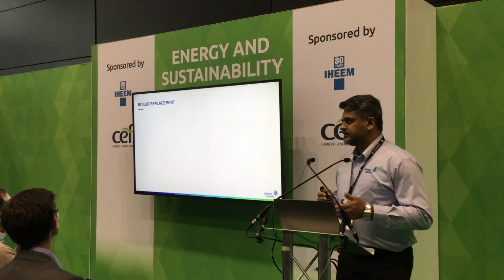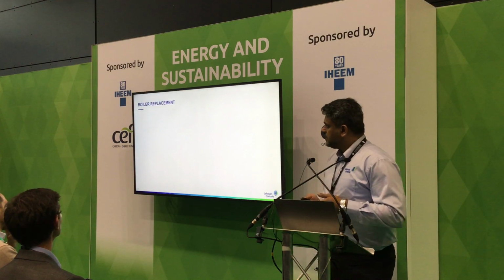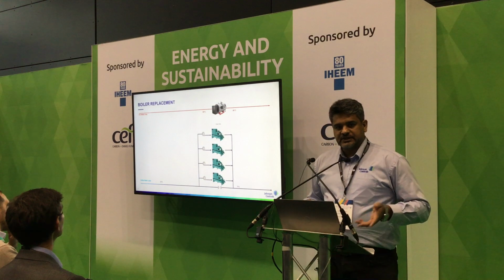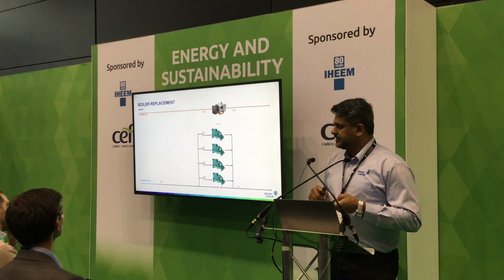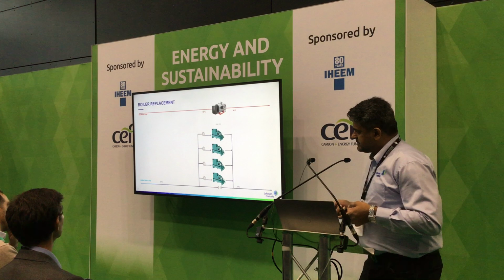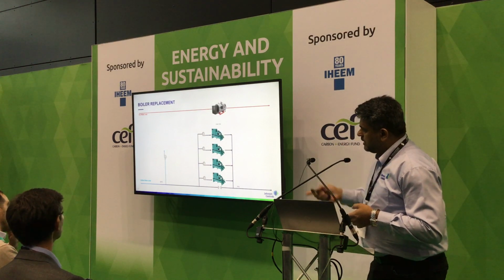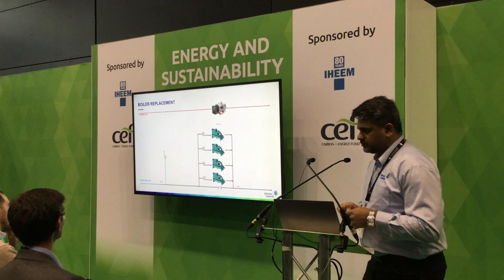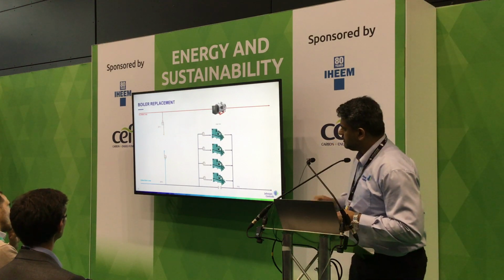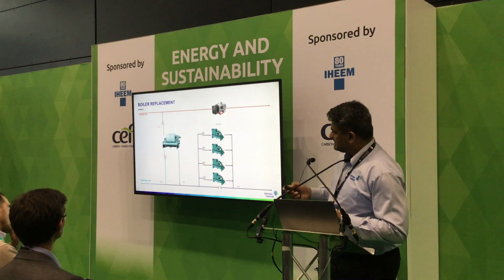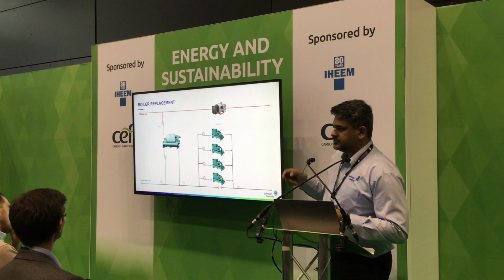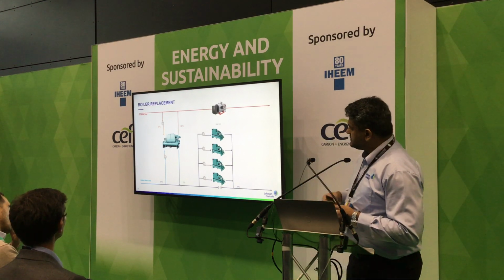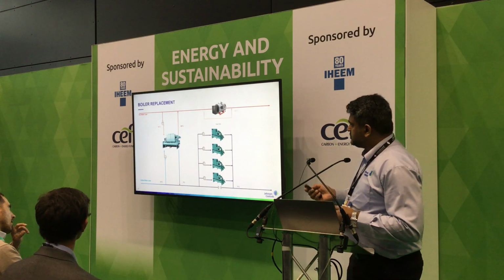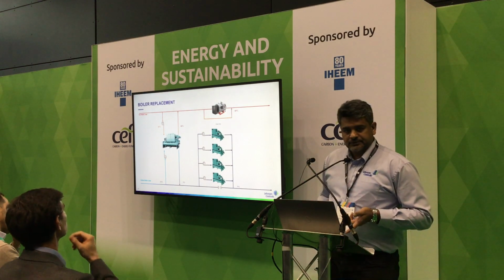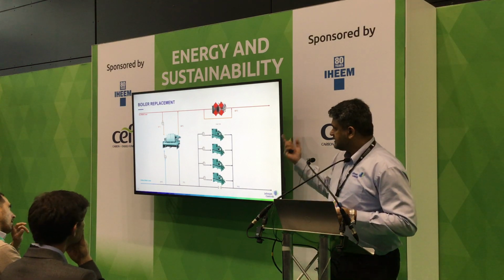Applications. Typically you would find a boiler replacement project. In old facilities you might have separate loops for both heating and cooling. What we find is if you can take return water from the chill water loop and return water from the hot water loop and run it through a heat pump, you can deliver lower temperature, 7 degrees, onto the chill water loop, and deliver up to 65 degrees on the hot water loop, which you can then use to bypass your boiler and eventually phase it out.